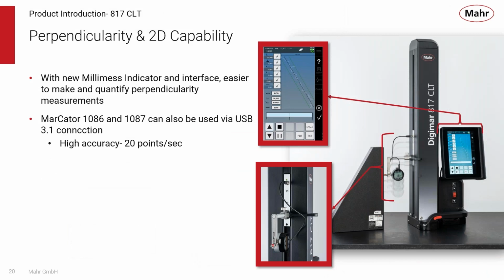As mentioned earlier, the 817 CLT is capable of perpendicularity and 2D measurements. It interfaces with the new Millimess indicator to easily quantify perpendicularity measurements, and can also work with Mahr's cheaper 1086 and 1087 digital indicators if the customer doesn't require the Millimess level of accuracy. Using a USB 3.1 connection, it collects 20 points per second for a very high resolution data set, with a simple, easy to use interface.